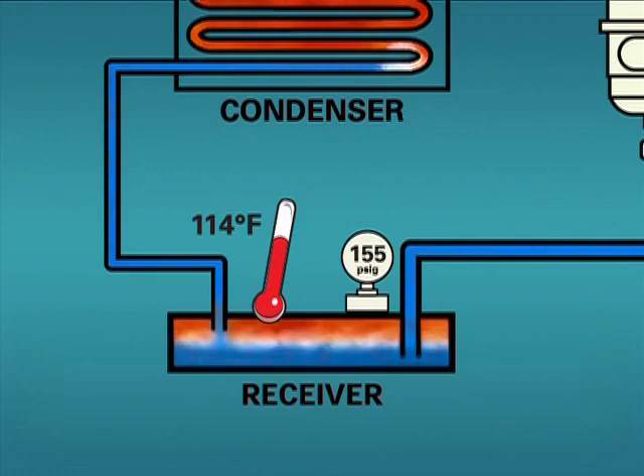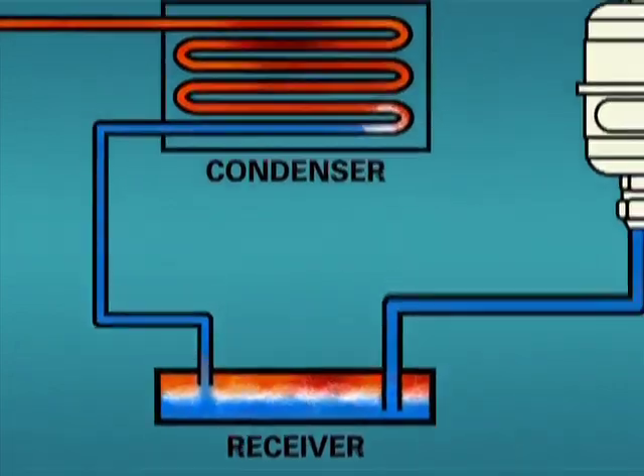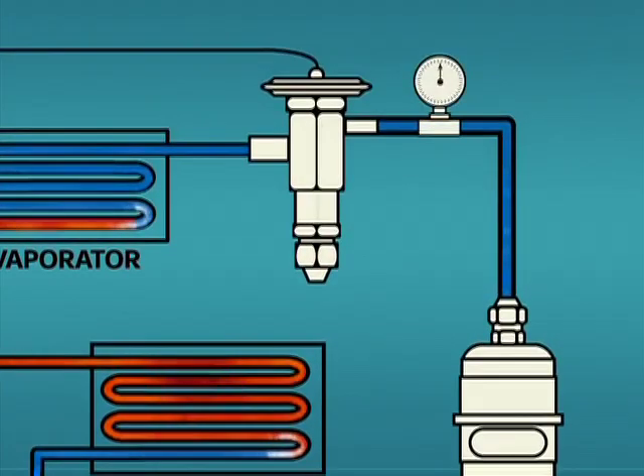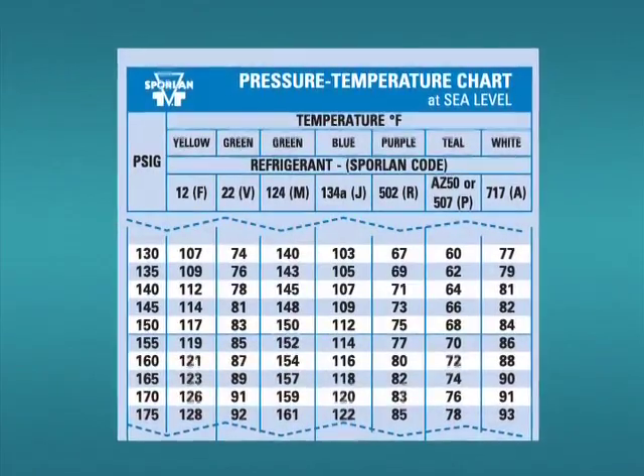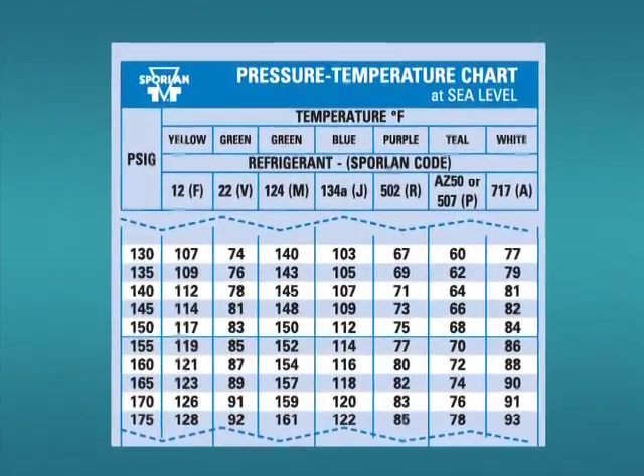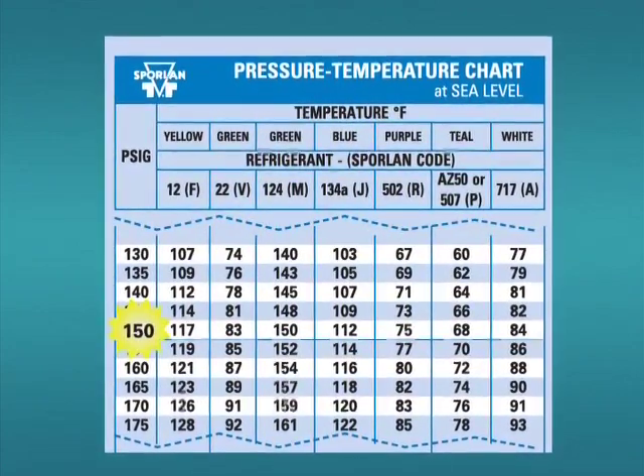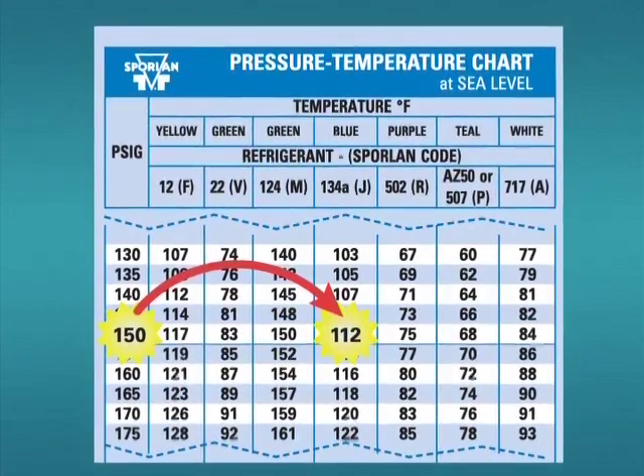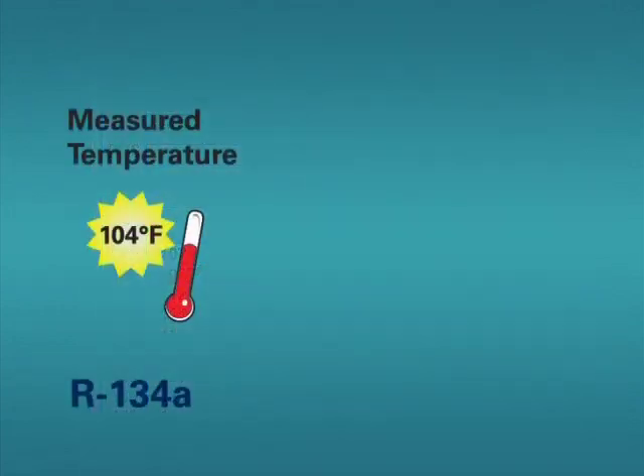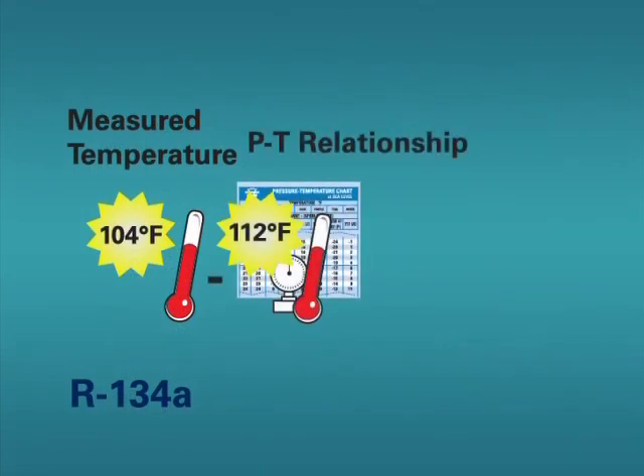Only the liquid vapor interface in the receiver must be at saturation. As another example, let's take readings at the TEV inlet. Our pressure gauge reads 150 PSIG and our measured temperature is 104 degrees Fahrenheit. To calculate our subcooling, we again reference our PT card. 150 PSIG on the PT card indicates a temperature of 112 degrees Fahrenheit. The difference between 112 degrees Fahrenheit and 104 degrees Fahrenheit is 8 degrees Fahrenheit subcooling.